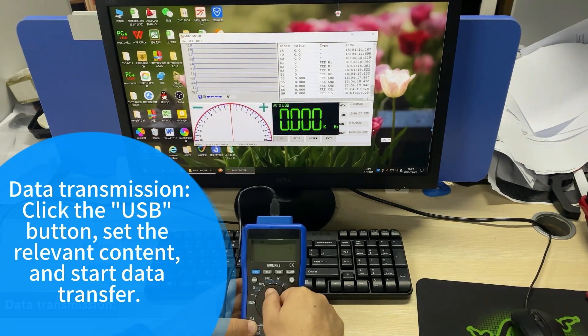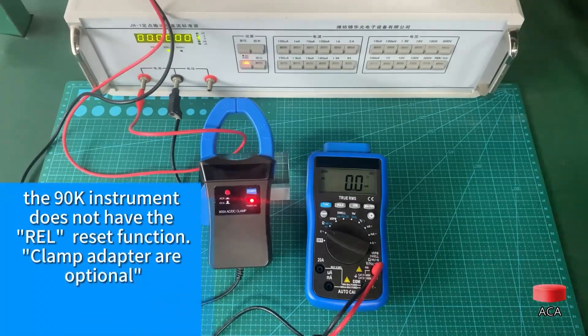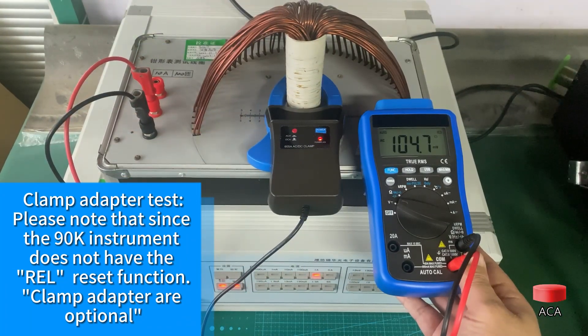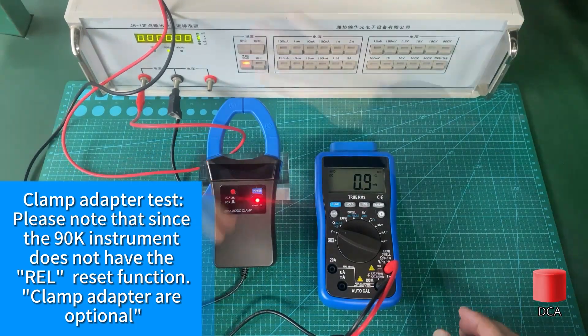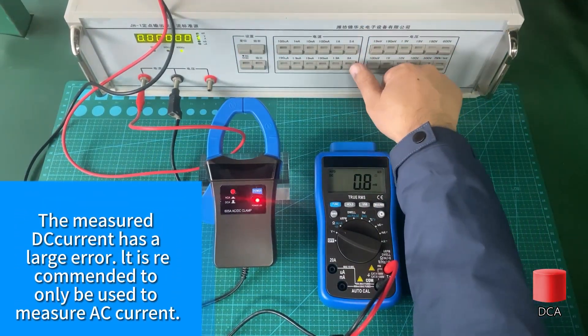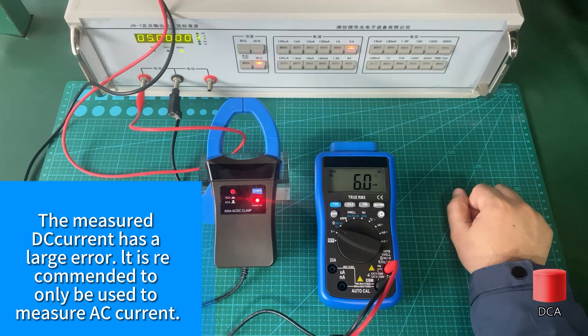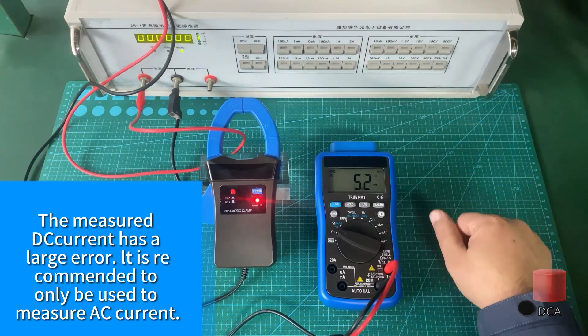Clamp adapter test: please note that since the 90K instrument does not have the REL reset function, clamp adapters are optional. Measured DC current has large error. It is recommended to only be used to measure AC current.